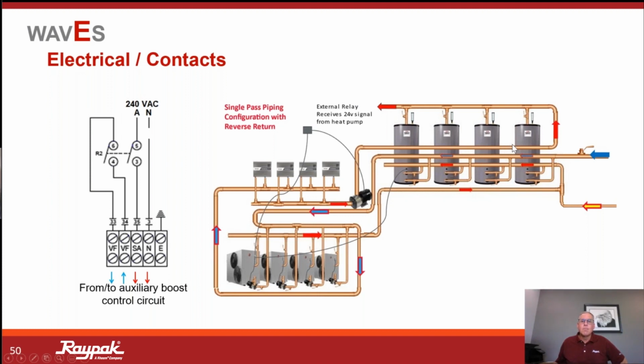Questions? Can I just make a slight comment? When dealing with electric tankless, ideally we want to make sure that pump is shown pumping into the supply side and not pulling on the outlet side. We want to maintain that pressure going through those tankless heaters. The inlet side of the pump is going to drop, and we don't want to do that. I concur. So what Randall is saying, this drawing, this circulator here on the suction side should be upstream of these heaters, and then the discharge side would be on the downstream, correct? Yes, that's what you're suggesting? Yes. Yeah, okay. I'll confirm. That's a good observation. Circulator placement on slide 50.